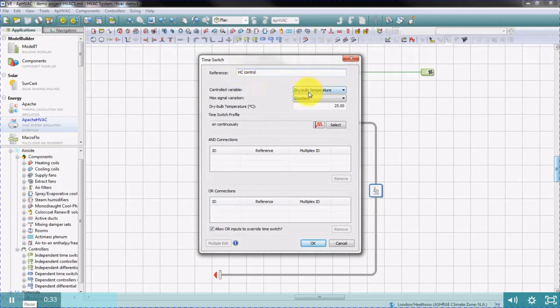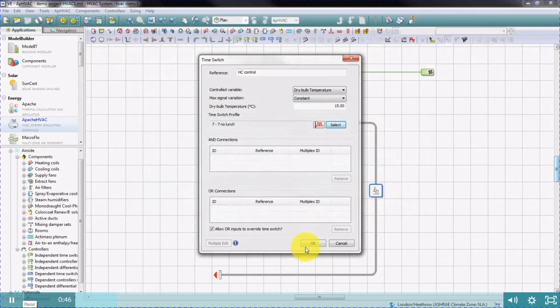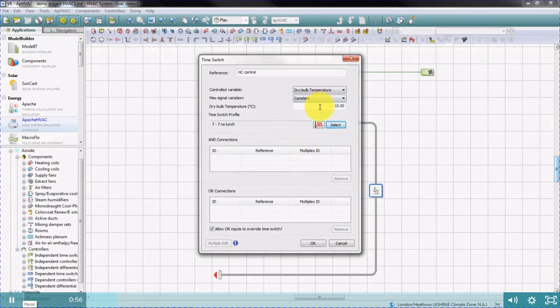We will control dry bulb temperature and enter the required off-coil dry bulb temperature, and when the control operates using a profile. This means that the heating coil will operate to achieve the required 15 degrees centigrade downstream of the heating coil. Of course, this is subject to the heating coil capacity, the capacity of the hot water loop that supplies it, and also the temperature before the coil.